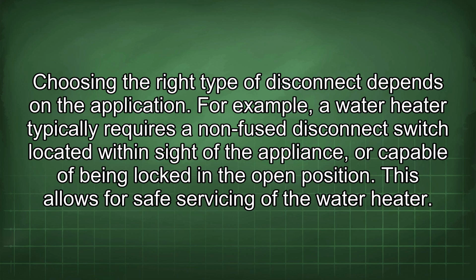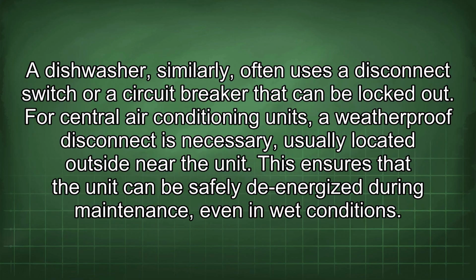Choosing the right type of disconnect depends on the application. For example, a water heater typically requires a non-fused disconnect switch located within sight of the appliance or capable of being locked in the open position. This allows for safe servicing of the water heater. A dishwasher, similarly, often uses a disconnect switch or a circuit breaker that can be locked out. For central air conditioning units, a weatherproof disconnect is necessary, usually located outside near the unit. This ensures that the unit can be safely de-energized during maintenance, even in wet conditions.